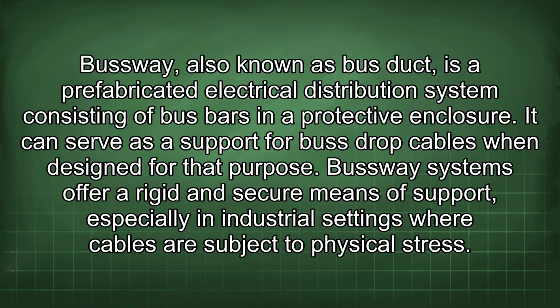Busway, also known as bus duct, is a prefabricated electrical distribution system consisting of bus bars in a protective enclosure. It can serve as a support for bus drop cables when designed for that purpose. Busway systems offer a rigid and secure means of support, especially in industrial settings where cables are subject to physical stress.